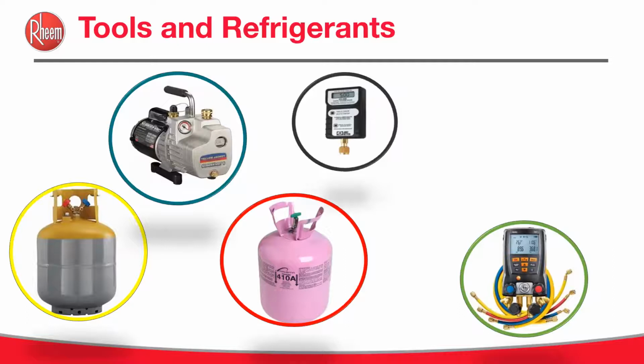There's new gauges out there that may be able to register microns, but you have to know what the micron level is. We recommend to pull down to 500 microns, and it should hold for a minimum of 15 minutes.